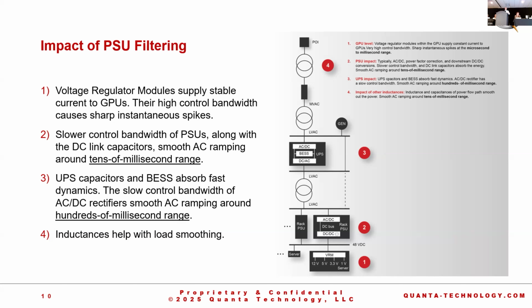Depending on the data center, you might also have a UPS, inline UPS or a double conversion UPS. They have capacitors, rectifiers, and relatively lower control bandwidths, so they smooth out the load even over hundreds of milliseconds. On top of that, number 4 is all the reactances and inductances that will also smooth out the load. So in short, what you'll see at location 4, the point of interconnection, is not going to be as extreme as what you have at location 1, but it's still problematic.